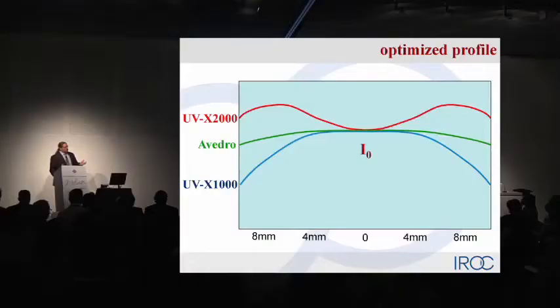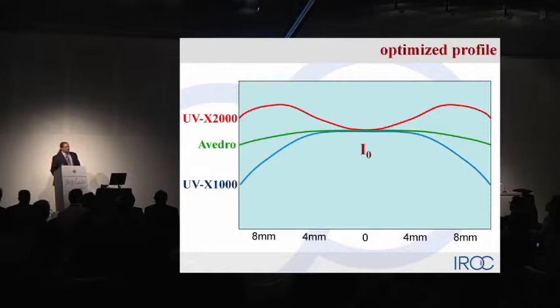How does this look? The initial cross-linking system we brought to market in 2007 had a pretty much Gaussian-like profile. We believe that adding more light intensity in the periphery — at about 8 mm and 6 mm in diameter — getting more cross-linking in the periphery over the thinnest point while keeping the same intensity in the center, will improve the outcomes. Compared to other systems which have more of a constant profile, we're doing about 25% to 30% more in the periphery with our cross-linking system.